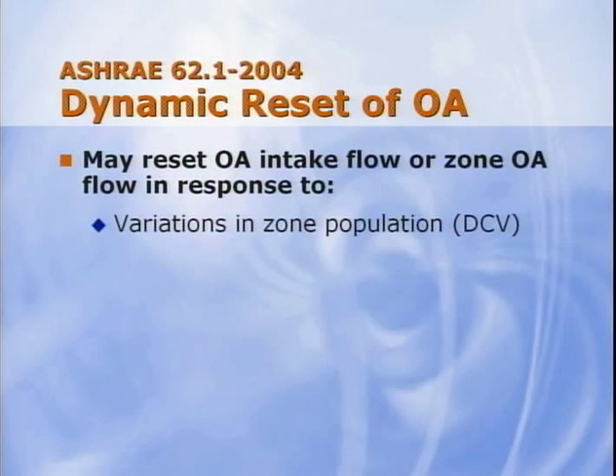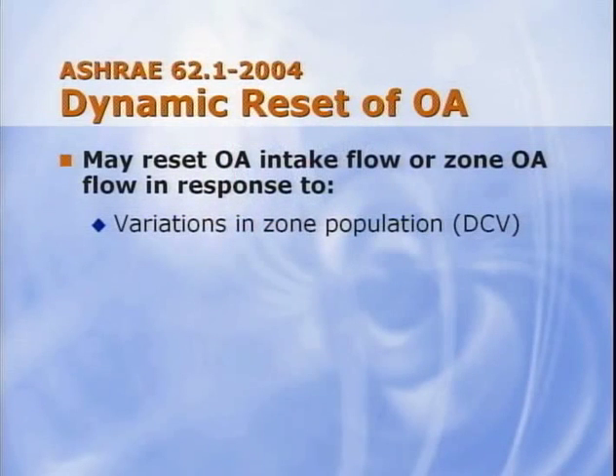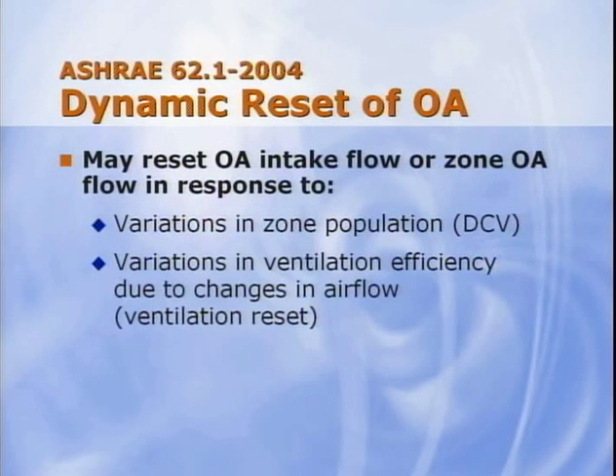You can reset intake airflow in response to variations in zone population, which is often referred to as demand-controlled ventilation. DCV is commonly implemented using carbon dioxide sensors, but occupancy sensors or time-of-day schedules can also be used. In addition, you can reset intake airflow based on variations in ventilation efficiency, which we refer to as ventilation reset. The goal of each of these strategies is to bring in only the minimum amount of outdoor air needed for the current system operating conditions. In most applications, reducing the outdoor airflow will save energy.